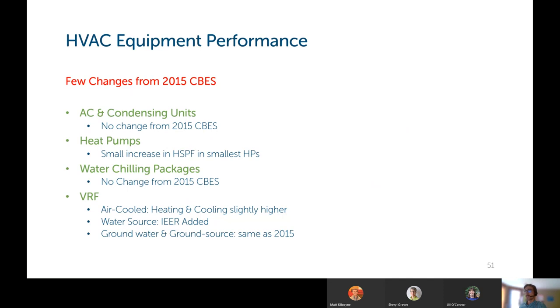The HVAC equipment performances have changed only slightly compared to the 2015 code. So these are all the tables that you typically see in the code stating all the heating and cooling efficiencies. AC and condensing units, there's been no changes from the 2015 code. Heat pumps, there was a small increase in the seasonal heating performance factor in the smallest of heat pumps. Water chilling packages, no change from the 2015 code. For VRF systems, if they're air cooled, the heating and cooling efficiencies are slightly higher. Water source VRFs on an IEER seasonal efficiency has been added, and ground water and ground source VRFs are the same efficiencies as 2015.